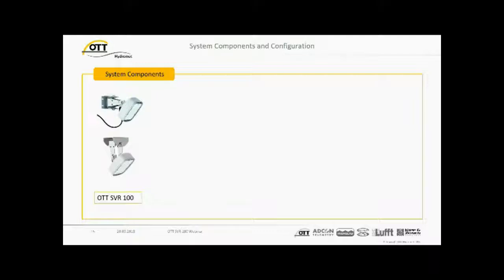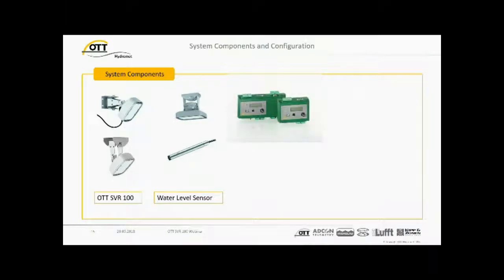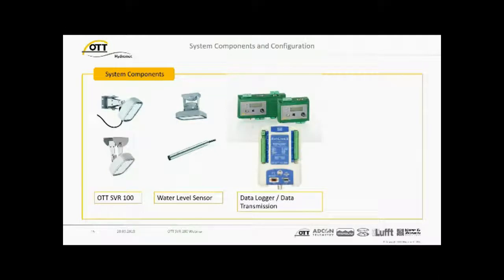Of course, first you need the SVR100 for measuring the surface velocity. Then you will need a level sensor because you need the cross-sectional area. You know, discharge is area times average velocity in the section, and for getting the area, you need a level measurement. You will need a data logger to compute the discharge. It could be a NetDL, it can also be a Sutlink, Sutron, so any data logger which is able to manage tables inside and has an RS485 interface can be used.